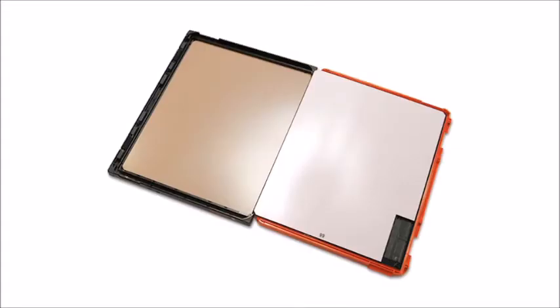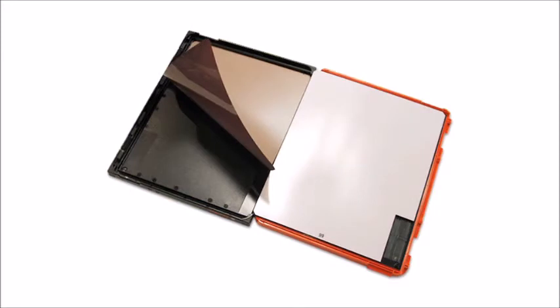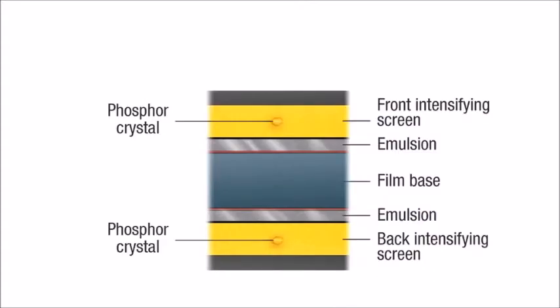The cassette in which film is placed is a shallow box lined with layers of felt or padding to press the film against the intensifying screens. Most cassettes have two intensifying screens. The film is placed between the two intensifying screens with the phosphor layer of each screen facing inwards in contact with the emulsion of the film.